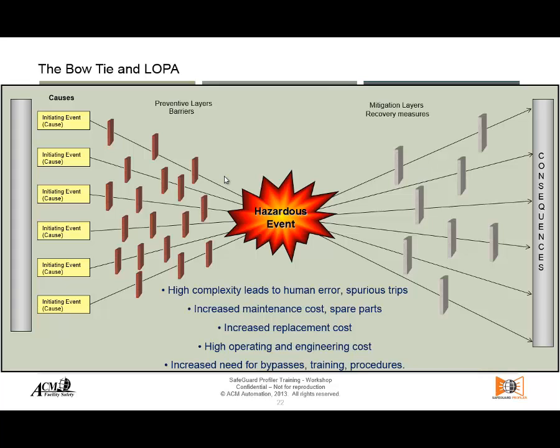False trips means stopping your plant unnecessarily because the system is too sensitive or too complex — the equipment is not interacting properly, so it stops all the time trying to be very safe. We need to simplify the system with respect to the amount of safeguards. If you have too many safeguards, you have to maintain all of them and make sure they are working in the right order. So how do we know if we really need them?